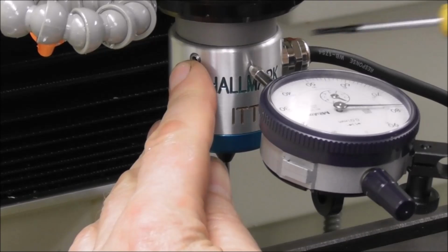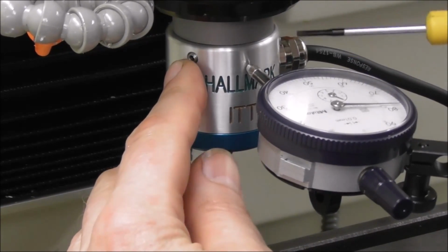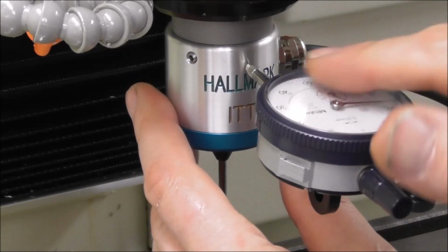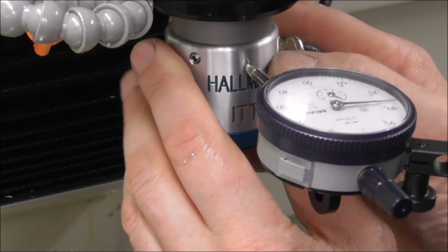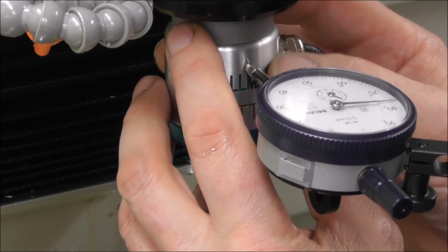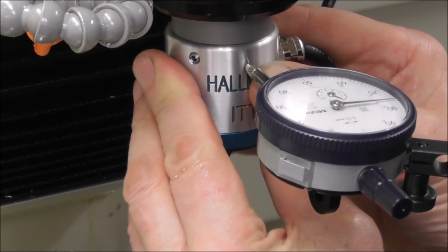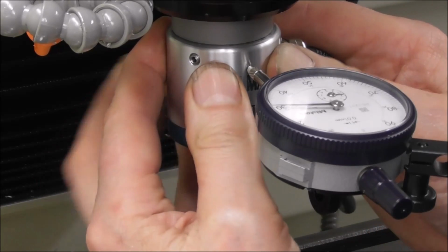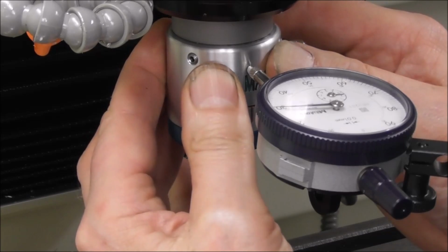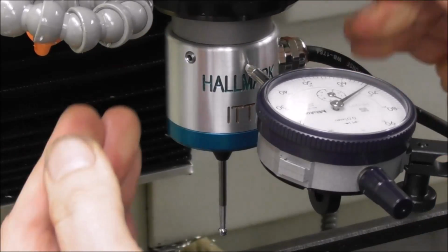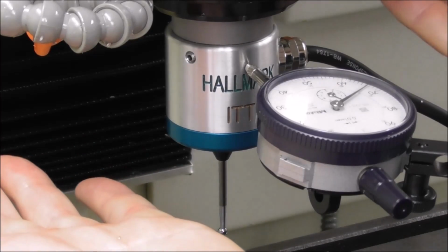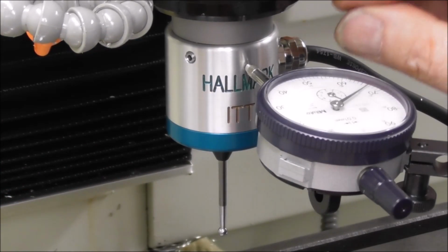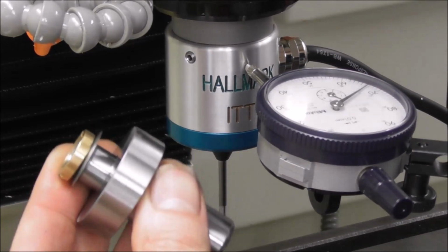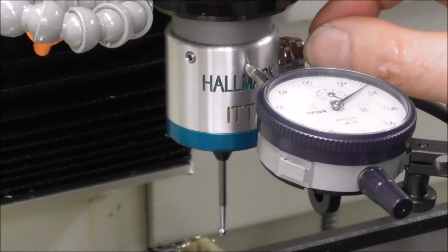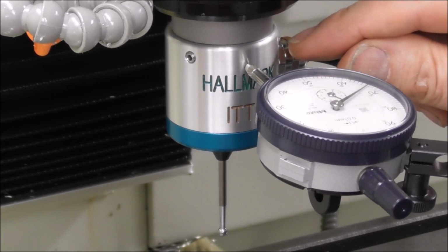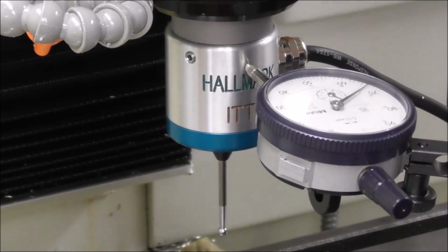Okay, well, there's 3 adjusting screws, and I've backed those right off so that I can show you with this dial indicator registering the movement how much adjustment there is with the body pre-tensioned to that shank. Let's have a look here. Hopefully you can see there's a big amount of adjustment, and it's pulled up against the flange of the shank. And so all we need to do, and it's pre-tensioned by that nut and that special spring washer, is to back off and tighten those 3 adjusting screws to get concentricity.